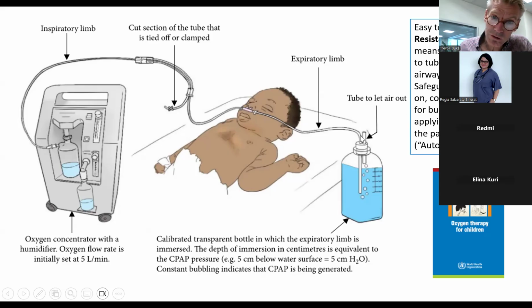Then you put the expiratory limb right underneath the water and you tie off the connection between the expiratory limb and the inspiratory limb. So you've got the gas flowing from the machine into the patient, and then as the patient breathes out, the air they breathe out is bubbled underneath the water. If it's 5 centimeters under the water, then they've got 5 centimeters of CPAP. They're still getting all the oxygen, or the gas flow, in. They can breathe out through their mouth, or they're also breathing out through the expiratory limb, and that goes under the water.